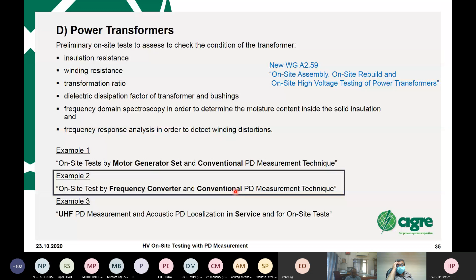Frequency converter. This is a special technology to produce a nearly perfect sine wave. The Q factor, the harmonic disturbance is below 5% because it's really a perfect sine wave. And the transformer PD activity was measured with a conventional PD measurement. That means a coupling capacitor was connected to the transformer to see what is going on. And here you see it's the on-site test. This is the device where the power electronics frequency converter is inside. In this case, a so-called applied voltage test was done. Applied means really high voltage was applied to the high voltage bushing side of the transformer.